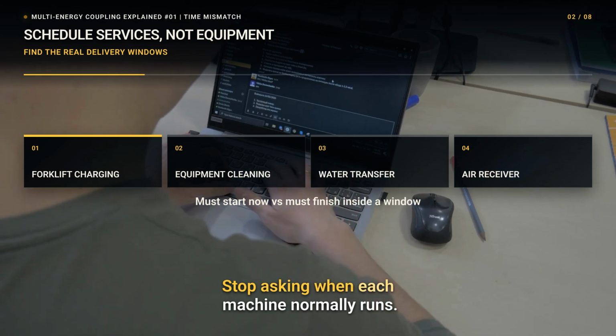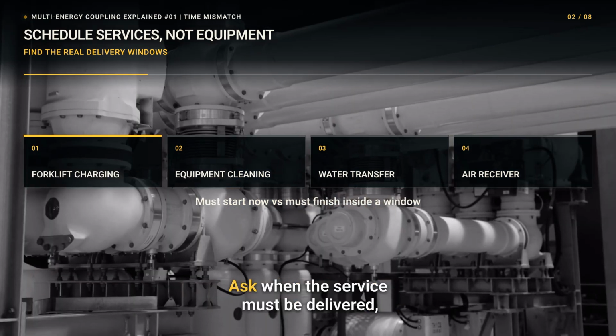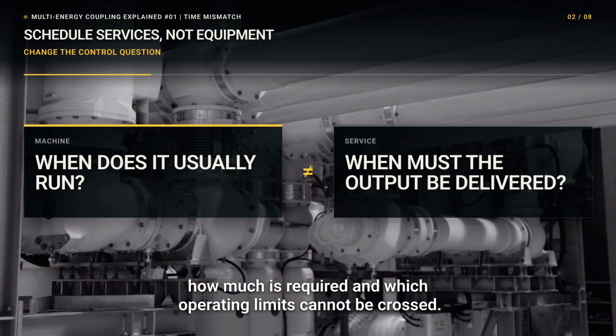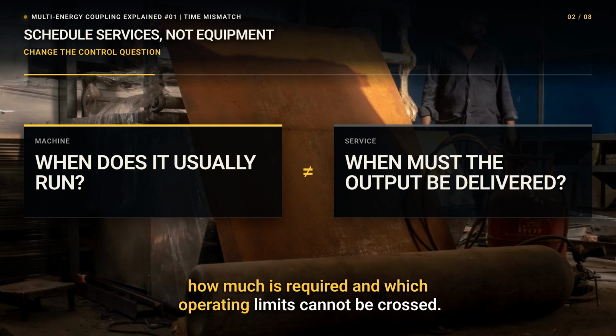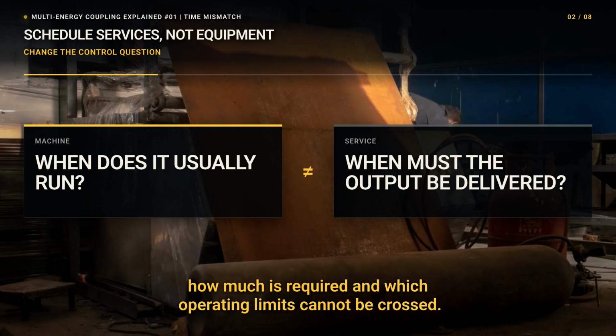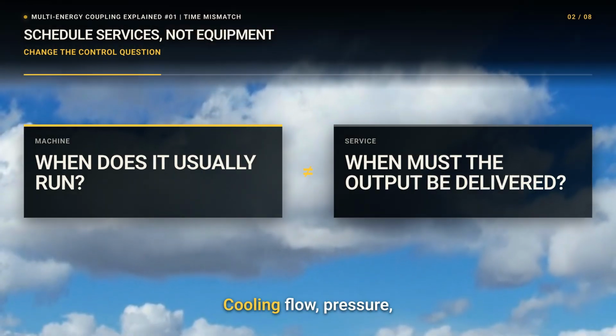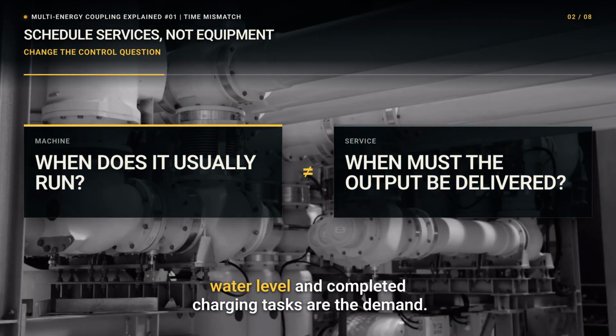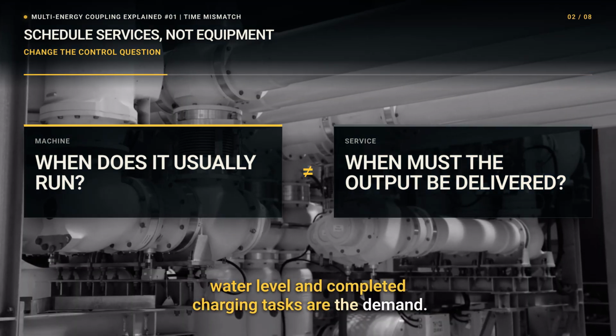Stop asking when each machine normally runs. Ask when the service must be delivered, how much is required, and which operating limits cannot be crossed. Machines are the means. Cooling, flow, pressure, water level, and completed charging tasks are the demand.